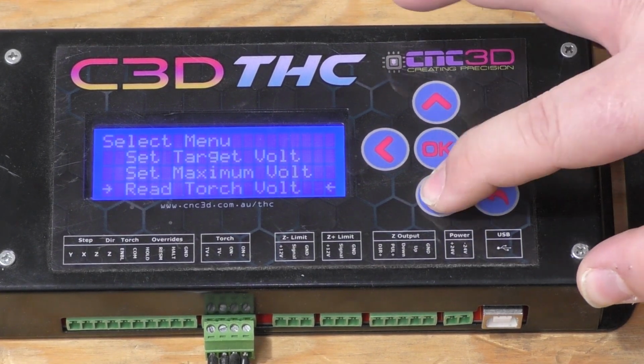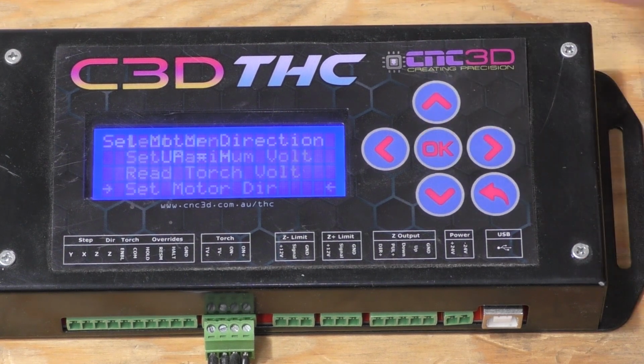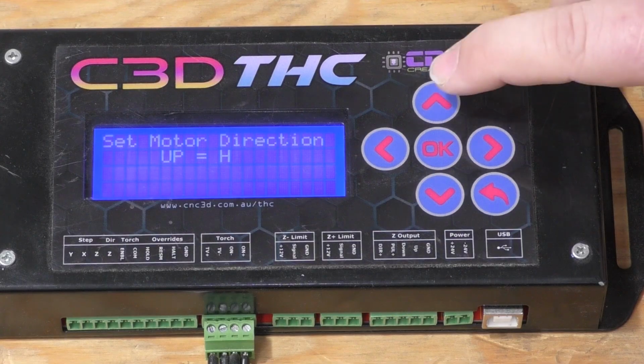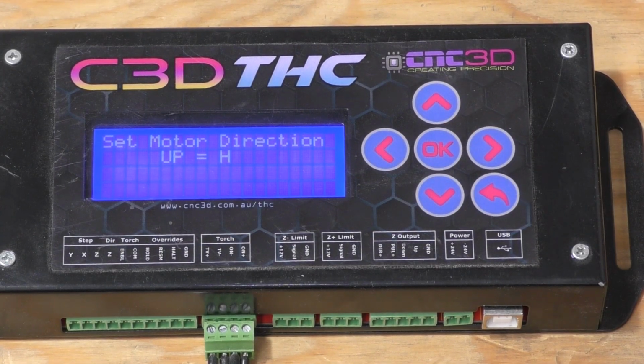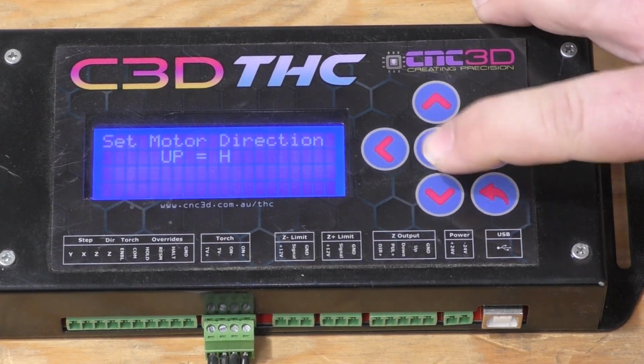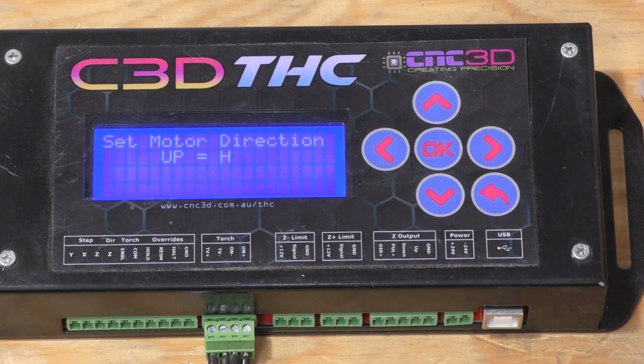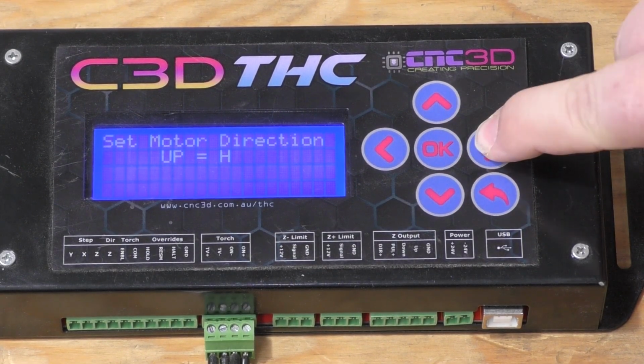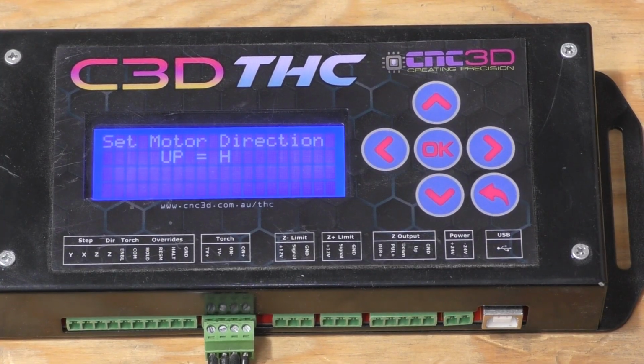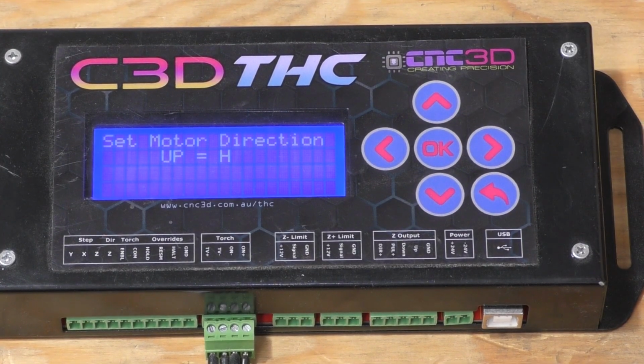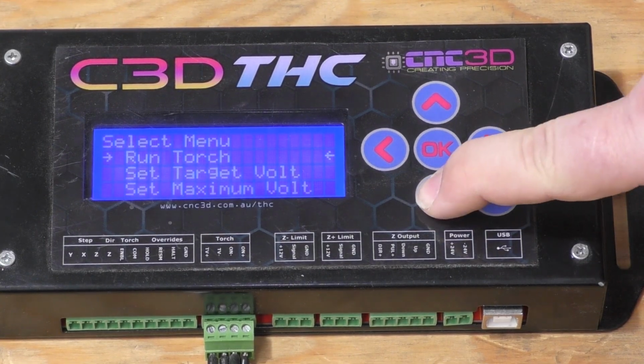The next one is set motor direction. Using this, you can adjust which way the motor turns. When you press the up button, your motor should go up. The down button should make the motor move down. If I press this up, you may be able to hear that motor moving. Down is the opposite. You can change these values using your left and right buttons. If your up button makes your motor go down, use left or right to change it to the opposite. And we'll go back.